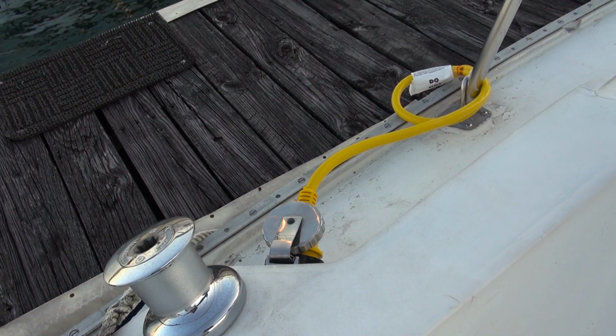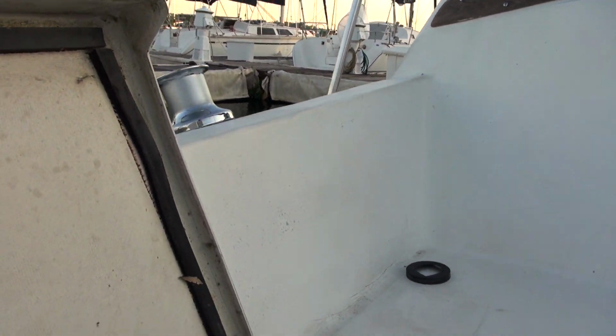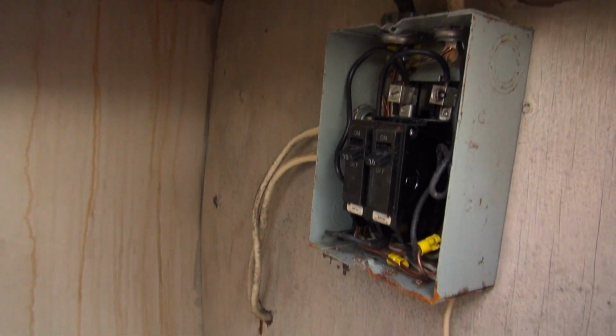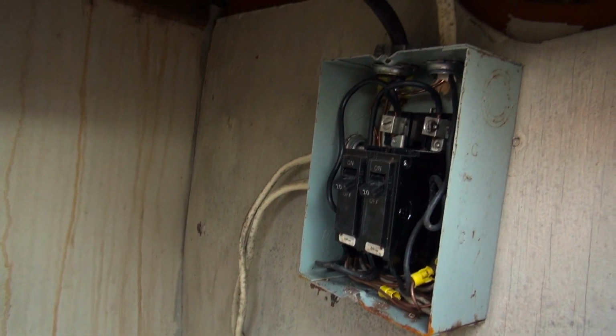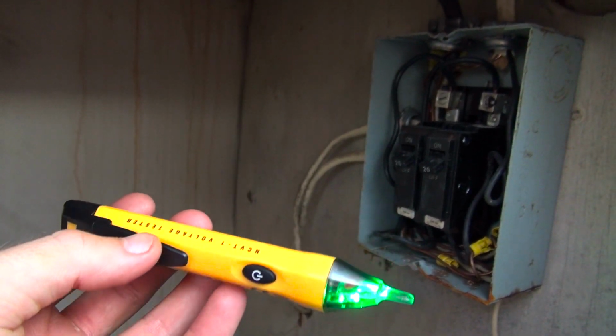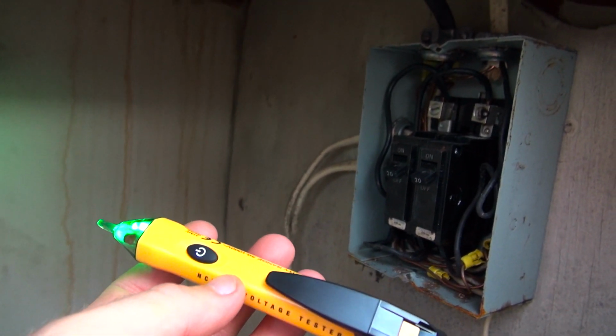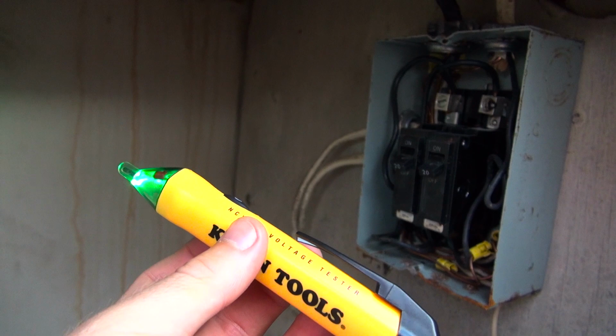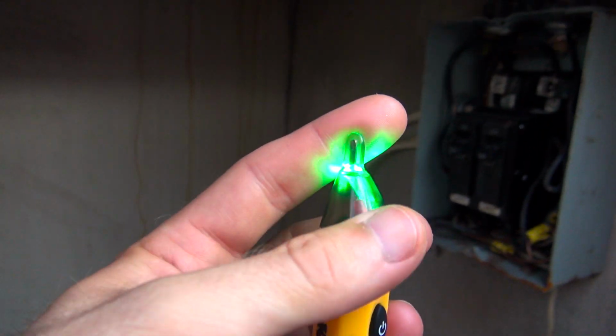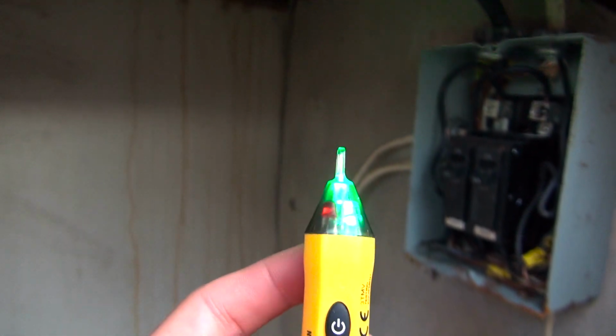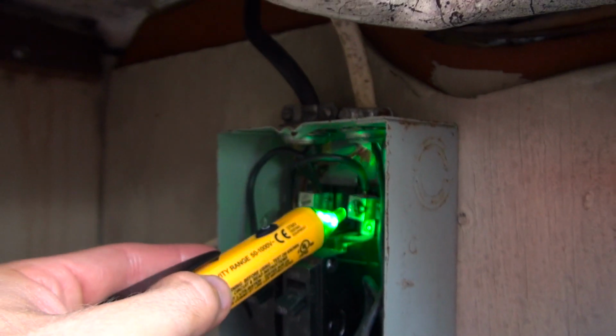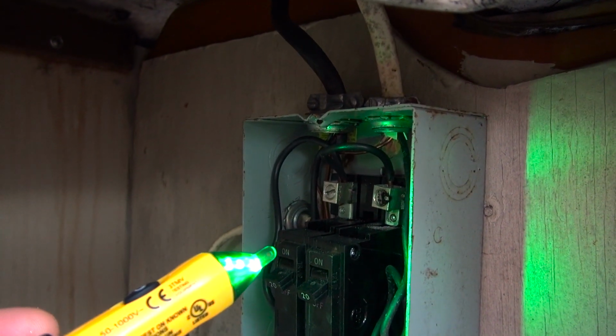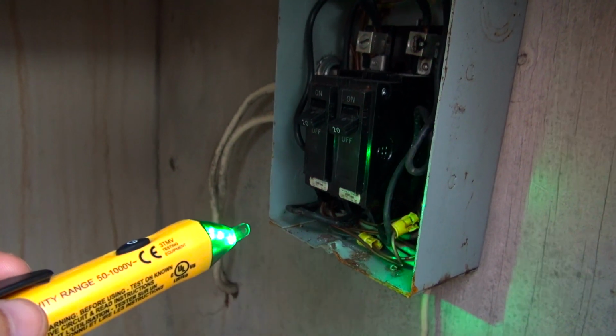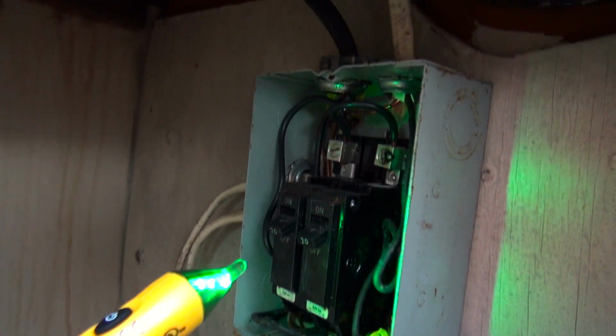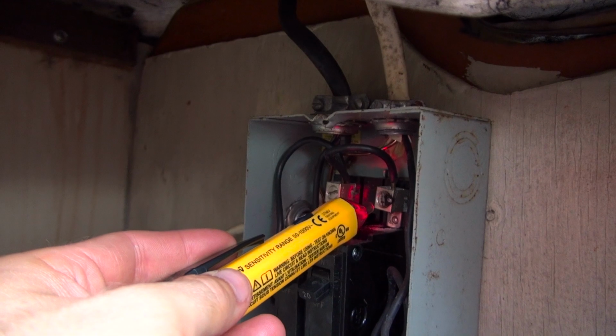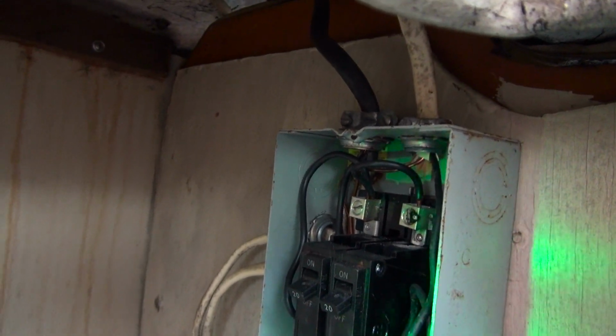I already troubleshot the actual receptacle, and it works just fine. To test whether voltage is coming through the breaker, I have a voltage tester that detects AC voltage within a certain proximity. It's covered in plastic so the metal doesn't touch anything, and it turns red if it senses power. As I get it close to the hot wire, the black is hot, the white is neutral, and the plain copper is ground. You always test the black, and you can see it's beeping and red, meaning there's voltage on that breaker.